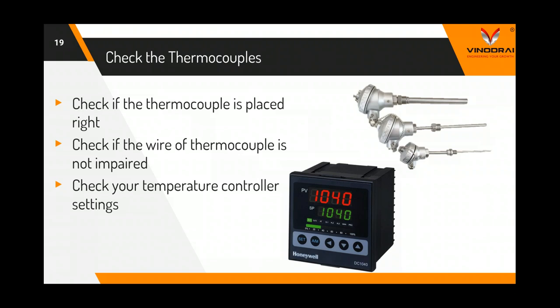Like the hysteresis temperature must be optimized to get a good temperature, to get a good fuel efficiency. Also, one of the main things is deposits on the thermocouple probe lead to false reading or may lead to readings with lag. So cleaning the thermocouple probe and the end regularly will give you a good result.